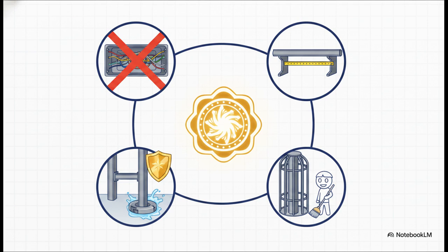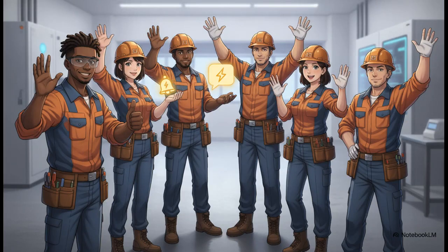Remember your 300-millimeter totally enclosed protection above floors. Keep that 15-meter and 1/3 ampacity tap reduction rule in your back pocket, and never ever use a splitter as a pull box for unrelated circuits. You know, mastering the code book isn't just about passing a test. It's about becoming a highly competent professional journeyperson who does the job right the very first time.